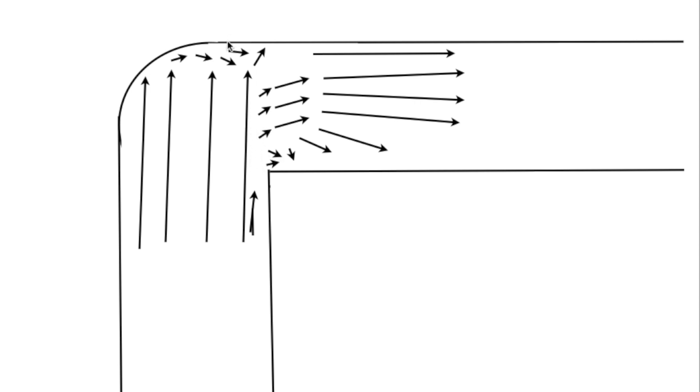As it bounces off up here it's going to build up some pressure. It's going to start tending to move the air this way, but this part right here is the part that has a lot of turbulence and that reduces the effective size of the ductwork by where that turbulence is. You can see the air kind of gets pushed up here and then starts coming down and spreading out again.